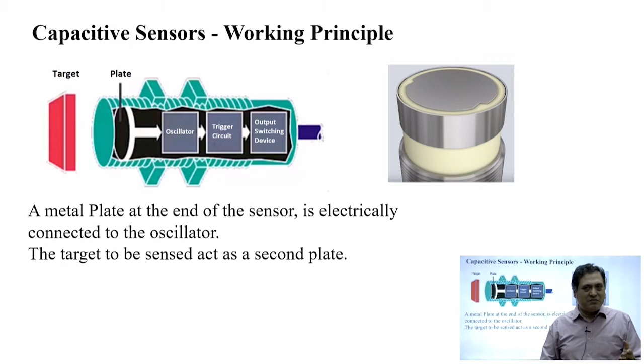The sensing face of the sensor acts as one plate of the capacitor, and the target material acts as the second plate of the capacitor. So, when the target approaches the sensor, the oscillator senses the presence of the target and starts oscillating at very high frequency, thereby causing a change in the external capacitance between the target and the sensing face of the sensor, which is captured by the trigger circuit, and then it generates an output.